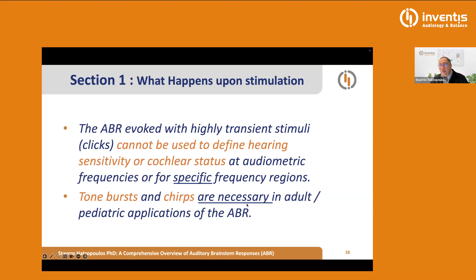Something really important to mention at this point is that the ABR responses evoked with transient stimuli such as clicks cannot be used to define the hearing sensitivity or the cochlear status at our audiometric frequencies, at our audiometric octaves, or in any specific frequency regions. The reason is that the click, as I explained before, tends to stimulate the whole cochlear partition. So if we need specific information from specific areas of the cochlea, we need to use other types of stimuli called tone bursts or chirps. These are mostly what we use in the pediatric and adult applications of ABR.